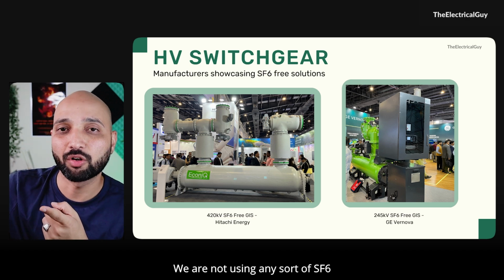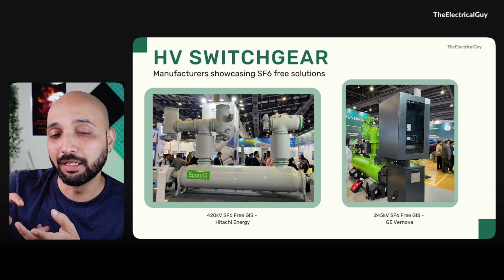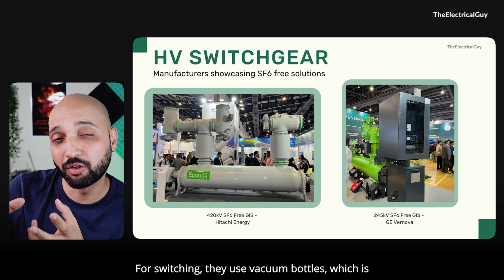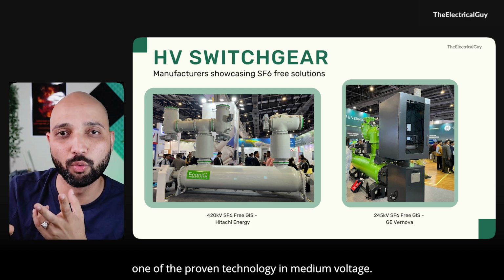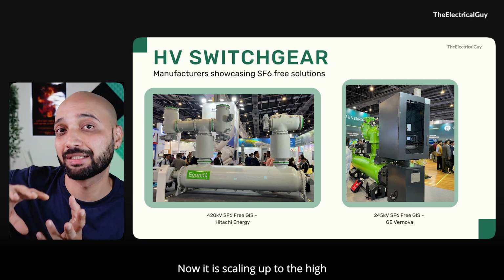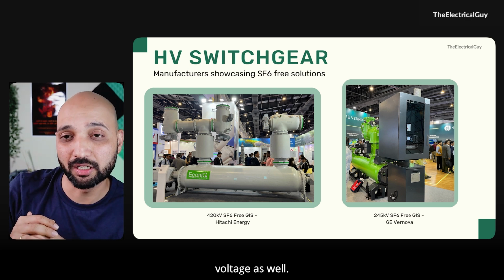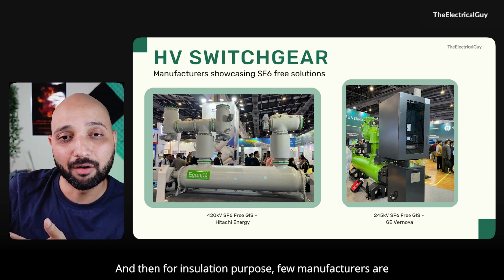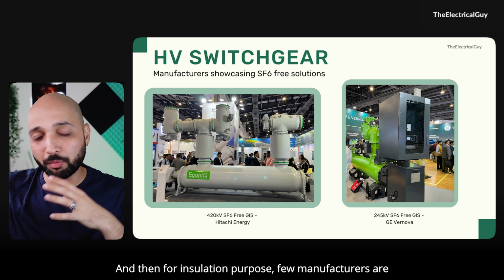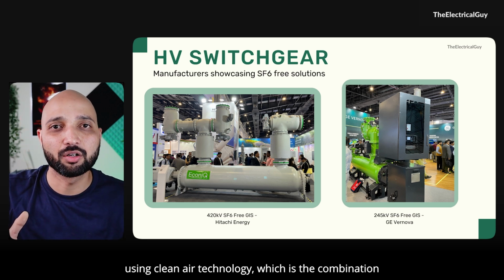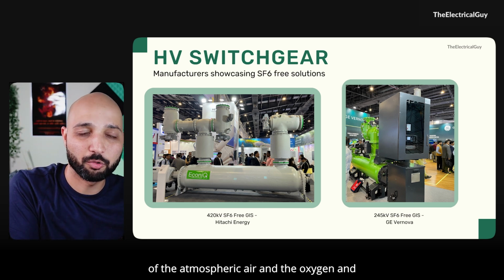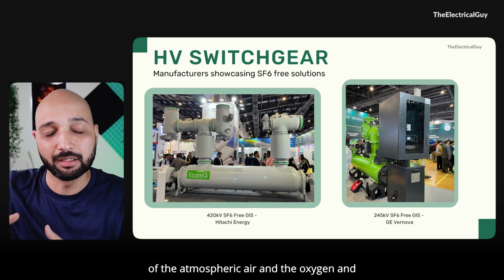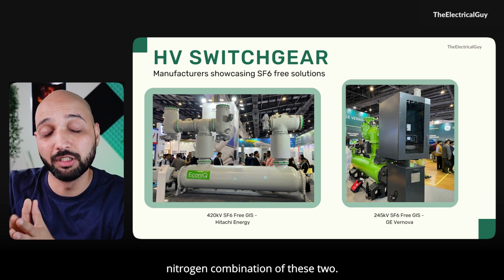That solution is available, not using any SF6 gas. They use vacuum bottles for switching, which is a proven technology in medium voltage, now scaling up to high voltage as well. For insulation, a few manufacturers are using clean air technology, which is a combination of atmospheric air, oxygen, and nitrogen.